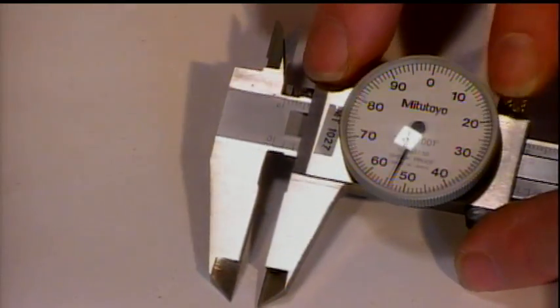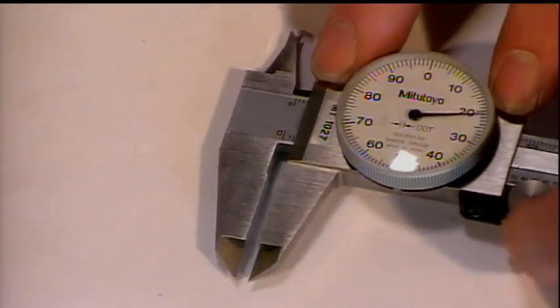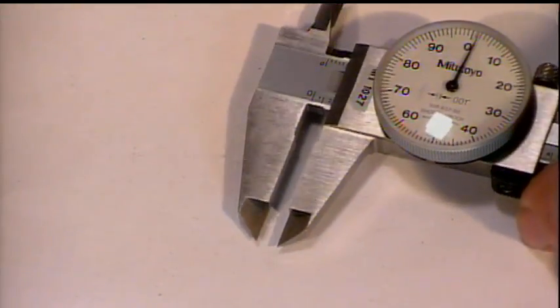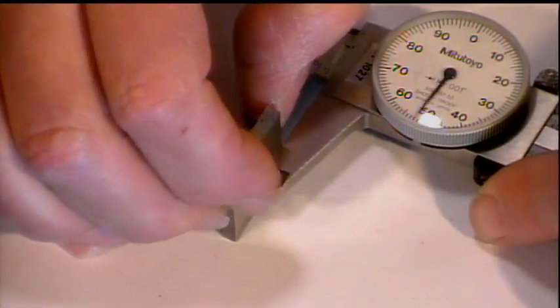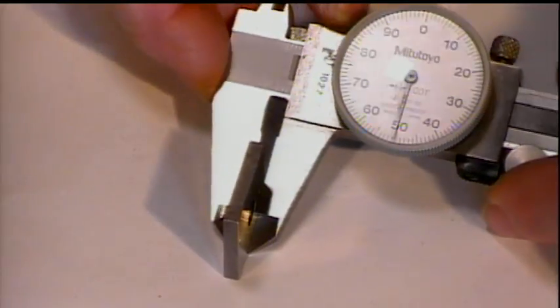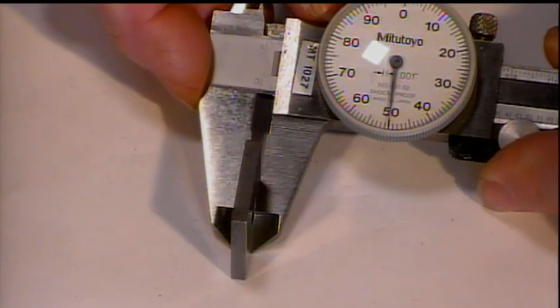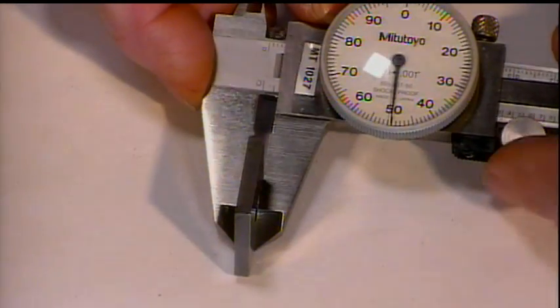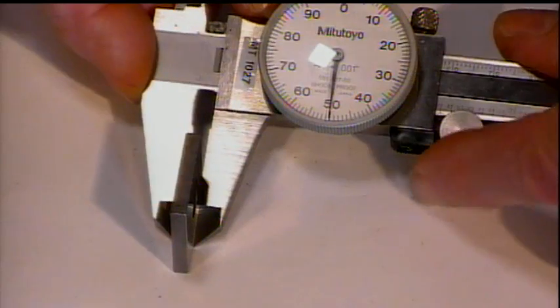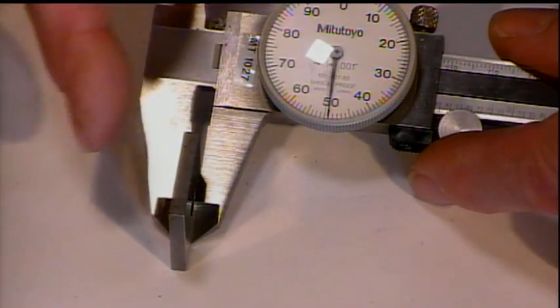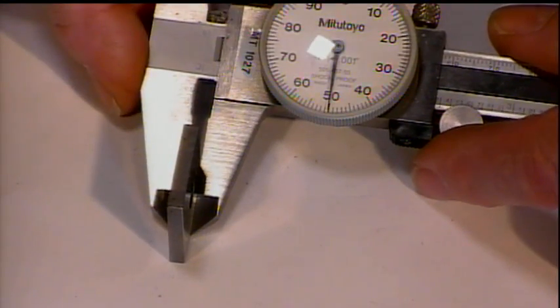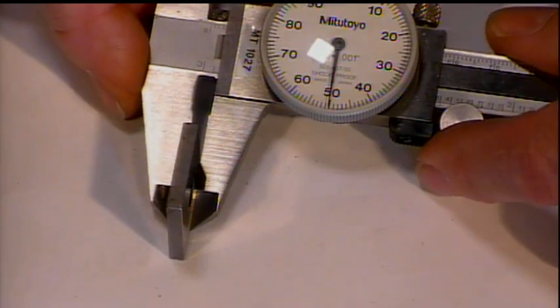Some minor gib adjustment might be needed, but that's how you could tell: if you're making a measurement and, depending on how hard you push, you keep getting a different number constantly. This one's adjusted pretty well. I'm putting tension on here and it's not moving. If that needle kept swiveling, you'd know something's up.